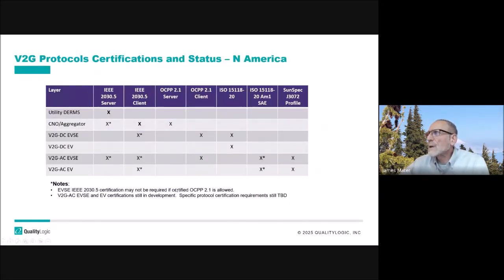I put together a table to help people understand what certifications are available today and what certifications need to be done in order to support V2G. So I've got the utility, the CNO, and both forms of V2G, whether it's DC or AC, with check marks where IEEE 2030.5 server needs to be certified or could be certified. I've got some footnotes noting that the certification may not be required if it's certified to OCPP 2.1. So that's still to be determined.